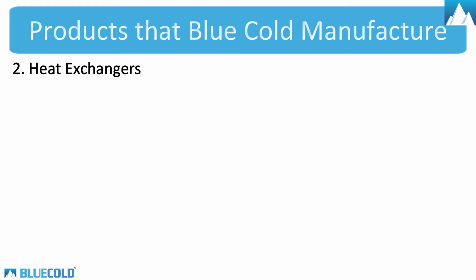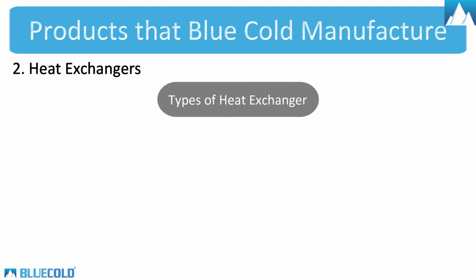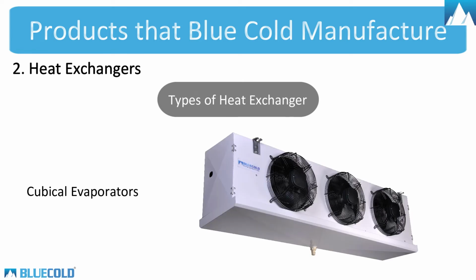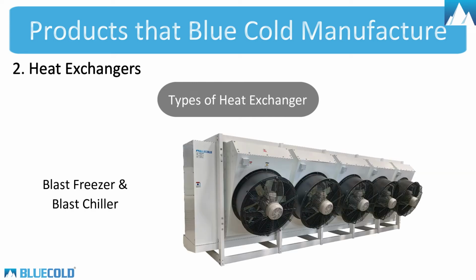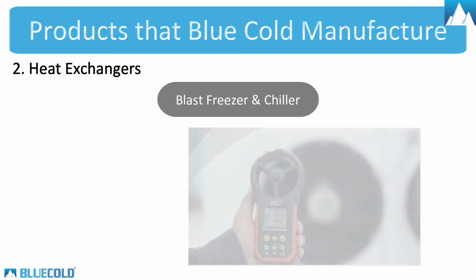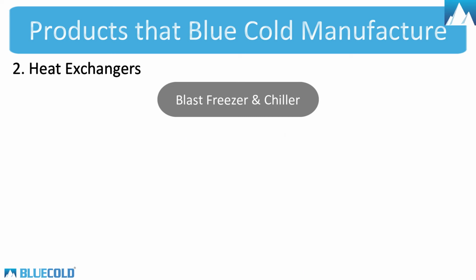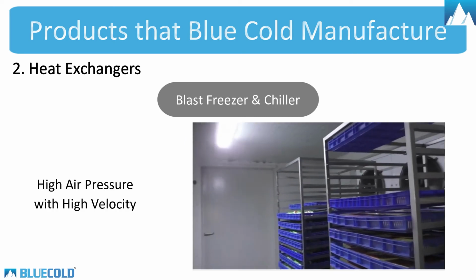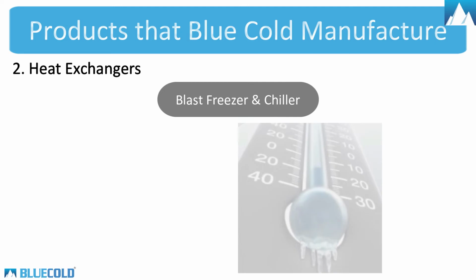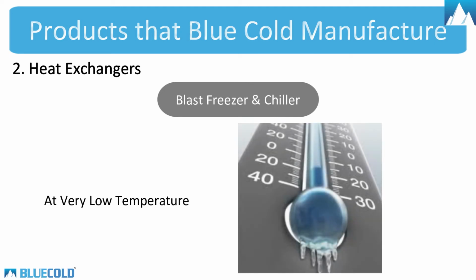Now let's look at the different kinds of heat exchangers we manufacture. Cubicle evaporators. It's a regular cold room evaporator that is responsible to deliver the required temperature and airthrow inside the chamber. Blast freezer and blast chiller. A blast unit has the following objectives: deliver high volume of airflow at high air pressure with high velocity at very low temperatures, sometimes at -45 degrees Celsius.